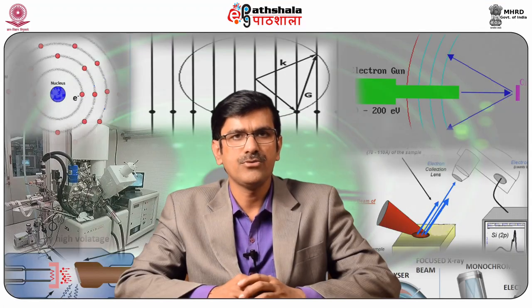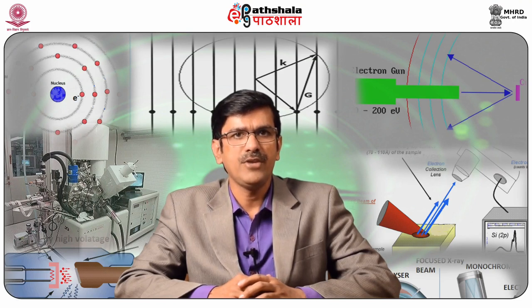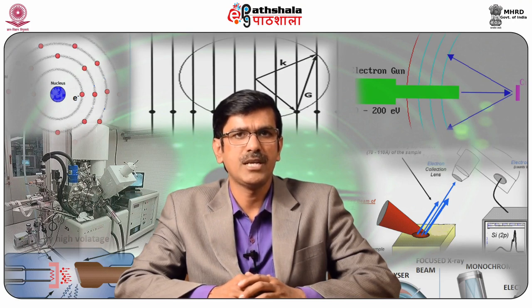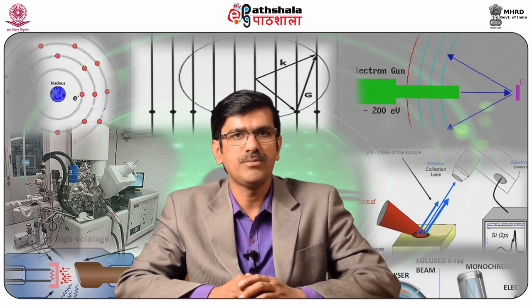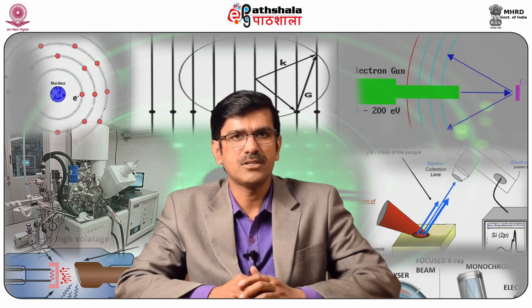Why is ultra-high vacuum required? UHV is of the order of 10⁻¹¹ Torr pressure. It removes adsorbed gases from the sample surface, eliminates adsorption of contaminants on the sample surface, prevents arcing and high voltage breakdown, and increases the mean free path of electrons, ions and photons.